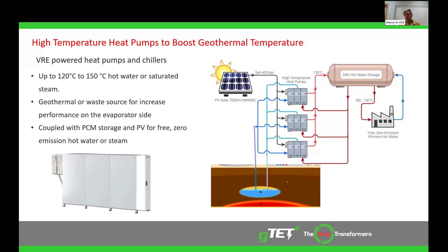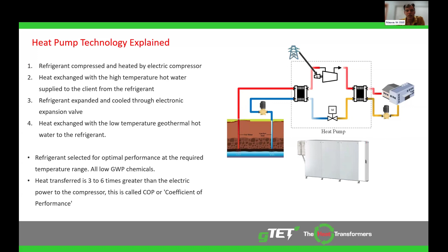I'm assuming everybody watching knows how a heat pump works, but specifically in this case we're taking the water and putting it into the evaporator. That makes it much better than an air source heat pump because the approach of the heat exchange is much closer, so it's much better and you can lift it up much higher. Industrial processes generally use a small delta T on the hot side, maybe only 5 degrees, so we generally prefer low GWP HFO refrigerants — they work well there. CO2 refrigerants are really good at lifting an ambient water supply up and making it quite warm, but if you're dealing in a 120 or 100 degree space, those HFO refrigerants seem to work better.